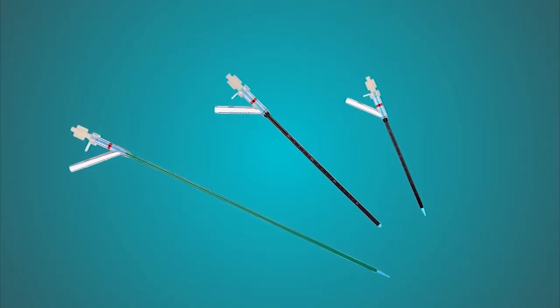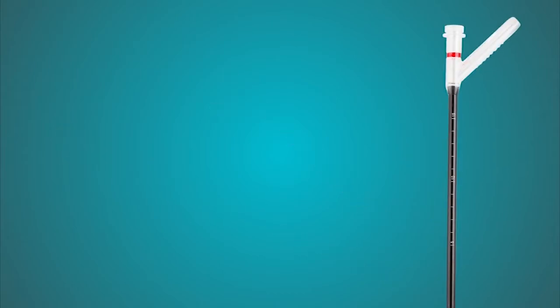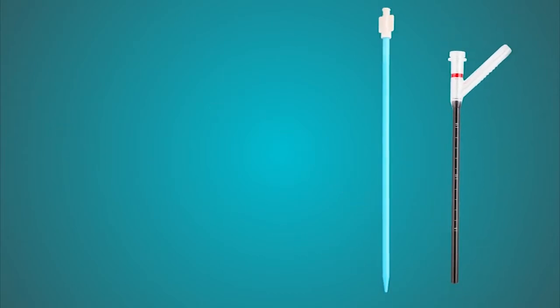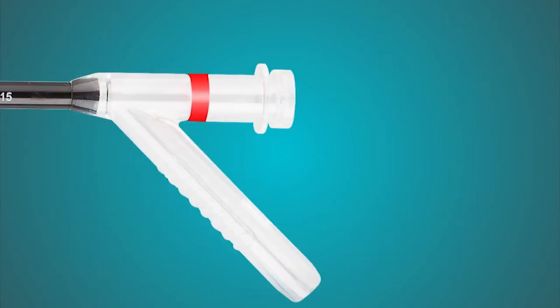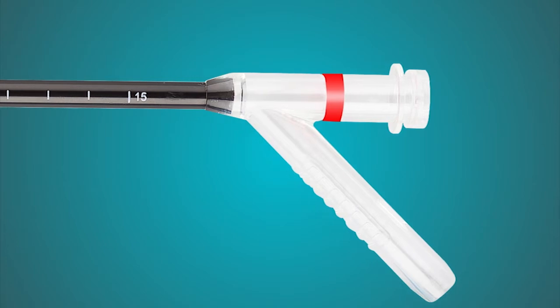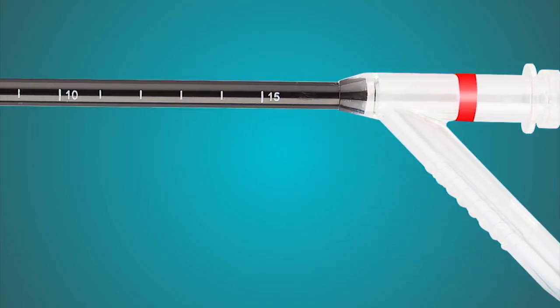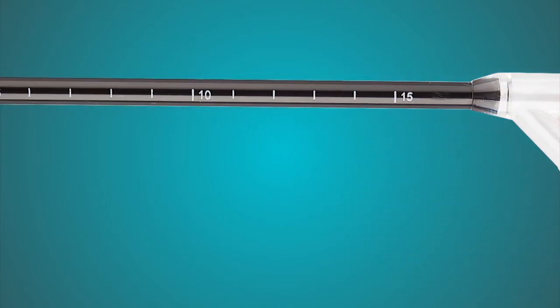The suction evacuation sheath consists of five parts: the sheath, the obturator, the rubber cap, the connection tubing, and the stone collection bottle. The sheath has a straight and an oblique proximal tubular section. It also has graduated centimeter markings.